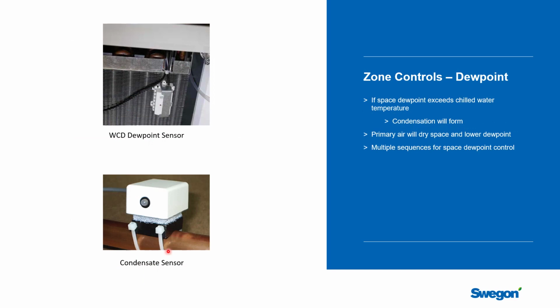Now, a lot of people are very interested in how you manage dew point control in a space, and that comes around because chilled beams are sensible devices. There are no drain pans, there is no condensate piping to a chilled beam, and so their purpose in life is to either add sensible heat or remove sensible heat as required for the space. They are not capable of removing humidity. That actually gets done with the primary air.